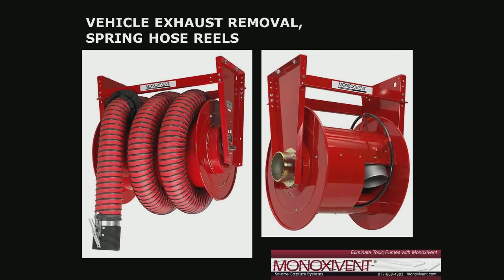Now, the hose stop on a spring hose reel is designed to stop it from recoiling when the adapter is about 6 to 6.5 feet off the floor. And the reason for that is that it has to be reachable by an average sized man or woman. So most of the time we determine that to be 6 or 6.5 feet off the floor. I'm going to show you a video that kind of demonstrates a spring hose reel, a little bit different application than an under chassis tailpipe. In this particular video, it will show you how you can utilize a spring hose reel on a vertical stack.